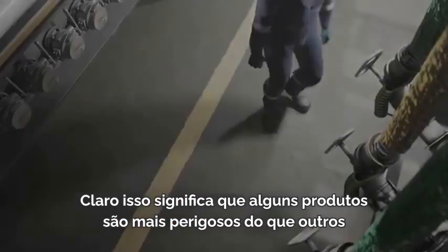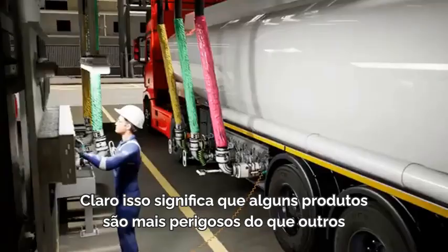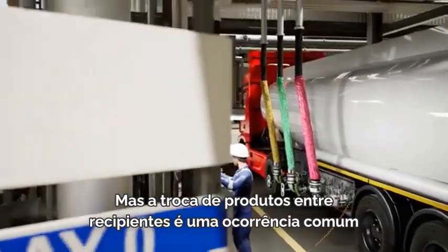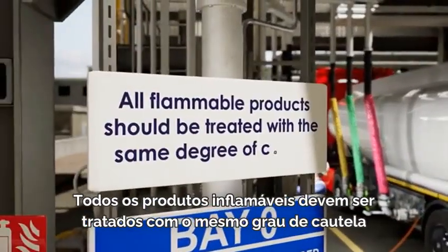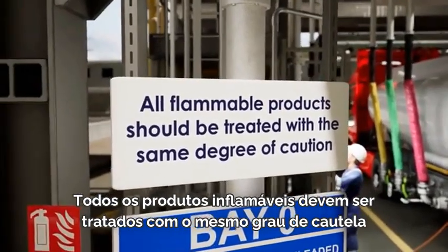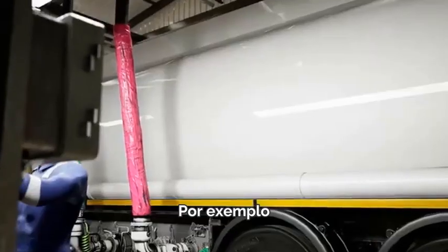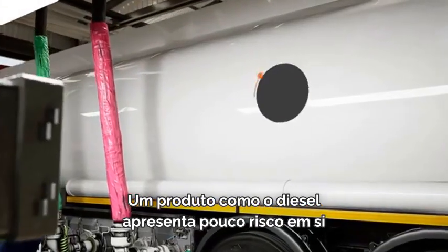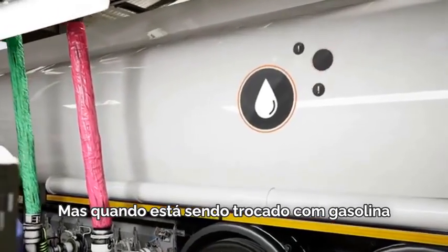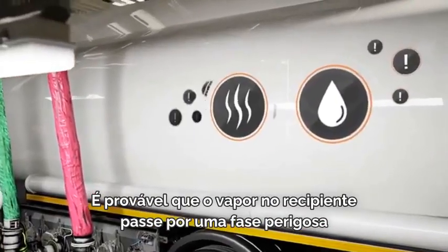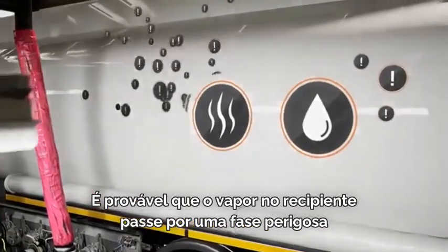Of course, this means that some products are more hazardous than others, but as switching products between containers is a common occurrence, all flammable products should be treated with the same degree of caution. For example, a product such as diesel poses little risk in itself, but when being switch-loaded with gasoline, it's probable that the vapor in the container will pass through a hazardous phase.